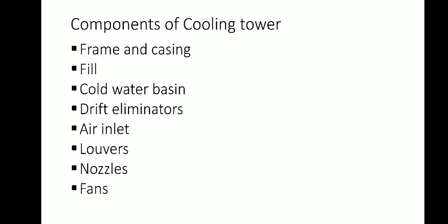The nozzles. These provide the water sprays to wet the fill. Uniform water distribution at the top of the fill is essential to achieve proper wetting of the entire fill surface. Nozzles can either be fixed in place and have either round or square spray patterns, or can be part of a rotating assembly as found in some circular cross-section towers.